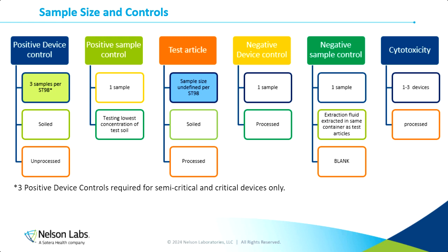The next discussion point is cytotoxicity. There's no requirement surrounding the sample size for cytotoxicity, but typically it is 1 to 3 devices. And these devices are those that will go through the cleaning process prior to that cytotoxicity test, just to ensure there's not any harm from detergent residuals remaining on the device that could essentially harm the next patient.